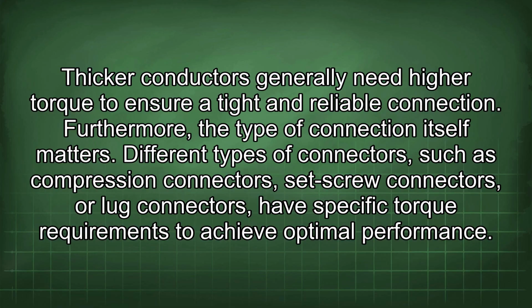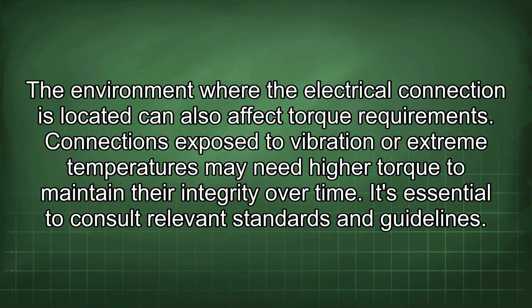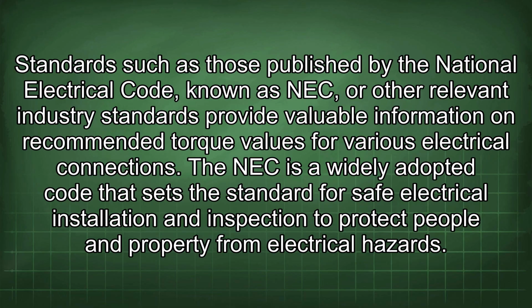Furthermore, the type of connection itself matters. Different types of connectors, such as compression connectors, set screw connectors, or lug connectors, have specific torque requirements to achieve optimal performance. The environment where the electrical connection is located can also affect torque requirements. Connections exposed to vibration or extreme temperatures may need high torque to maintain their integrity over time. It's essential to consult relevant standards and guidelines. Standards such as those published by the National Electrical Code, known as NEC, or other relevant industry standards provide valuable information on recommended torque values for various electrical connections. The NEC is a widely adopted code that sets the standard for safe electrical installation and inspection to protect people and property from electrical hazards.